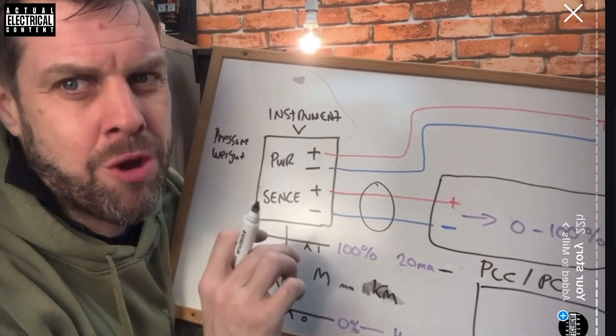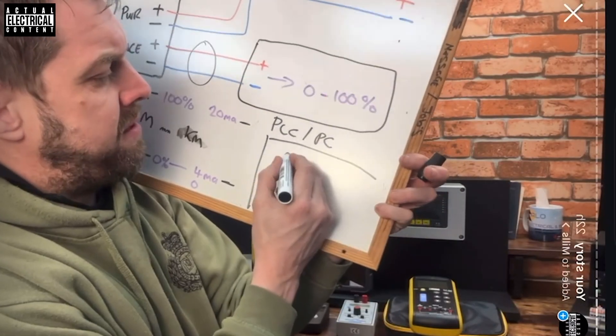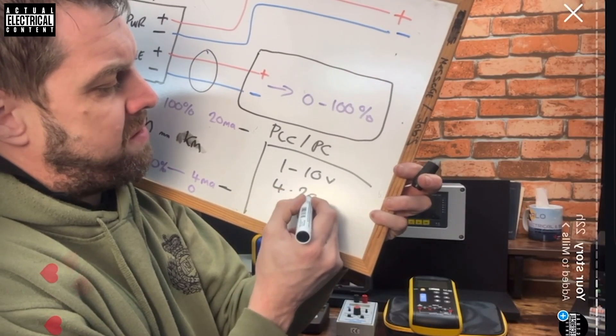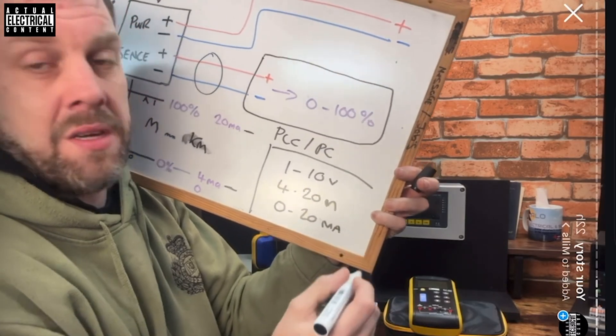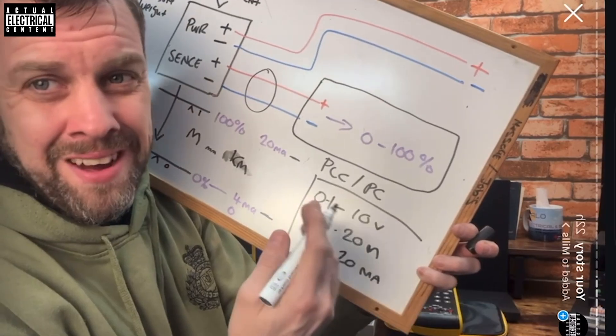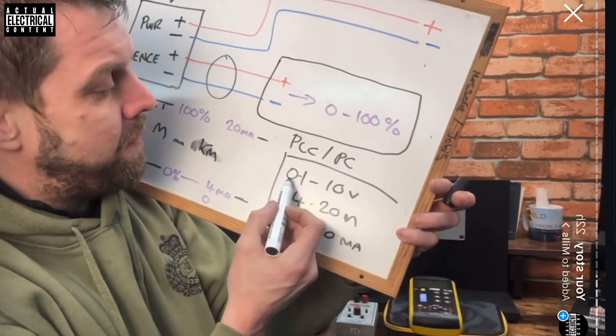Your instrument's all calibrated to measure between zero and one meter, but we need to move it to the control device, the PLC. We need to shift it and we're going to do that with milliamps. So what we do is we take the percentage and we convert it to milliamps. The lowest milliamp available - there's an exception to this in voltage as well - but I'm going to talk about 4 to 20 milliamps.